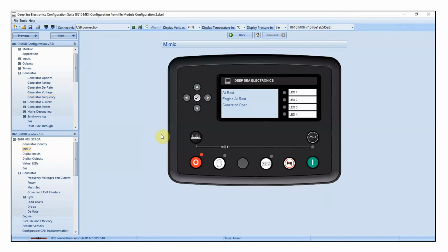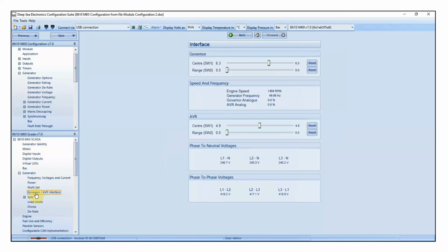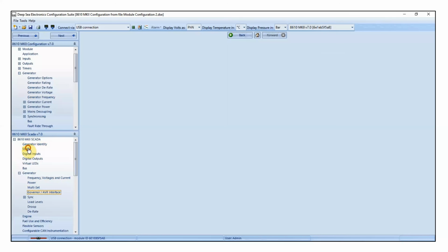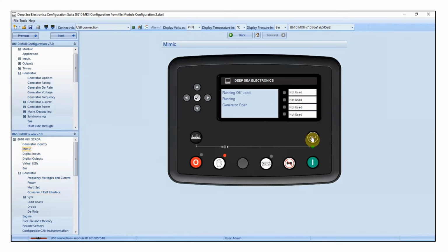This time we're going to start the generator, and as it runs with the breaker open, it will still run at 50 Hertz. When we close the generator's breaker, you will then see that the DSE module will start to try to adjust to 52 Hertz. So we're going to start, and you'll see that when I'm running with the genset breaker open, the generator is still running at 50 Hertz. As you can see here, still running at 50, not a problem. Then we're now going to close the generator breaker, and what should happen is we should see the frequency start to increase.